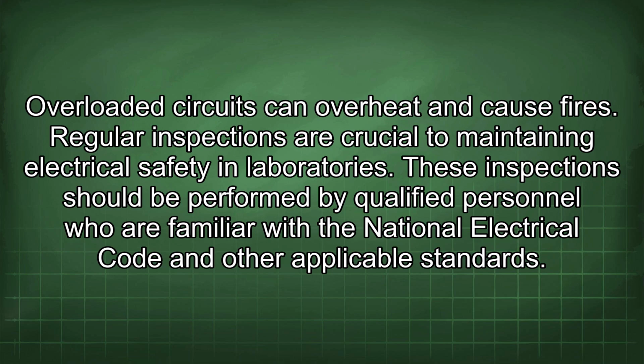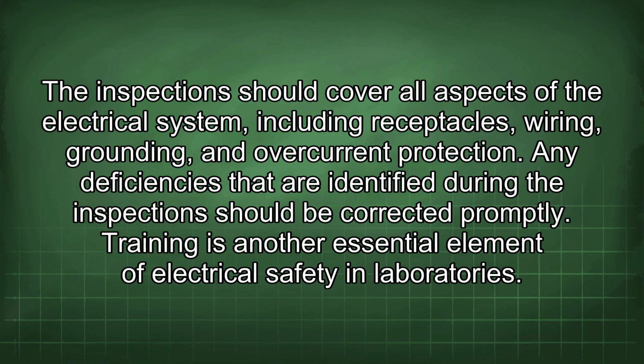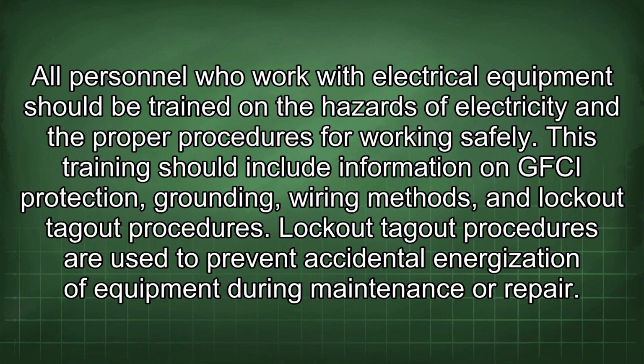Regular inspections are crucial to maintaining electrical safety in laboratories. These inspections should be performed by qualified personnel who are familiar with the National Electrical Code and other applicable standards. The inspections should cover all aspects of the electrical system, including receptacles, wiring, grounding, and overcurrent protection. Any deficiencies that are identified during the inspection should be corrected promptly. Training is another essential element of electrical safety in laboratories. All personnel who work with electrical equipment should be trained on the hazards of electricity and the proper procedures for working safely. This training should include information on GFCI protection, grounding, wiring methods, and lockout-tagout procedures.